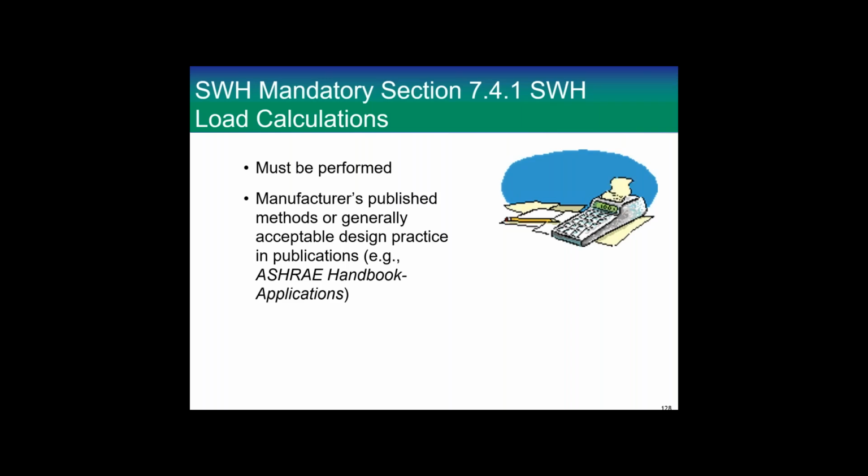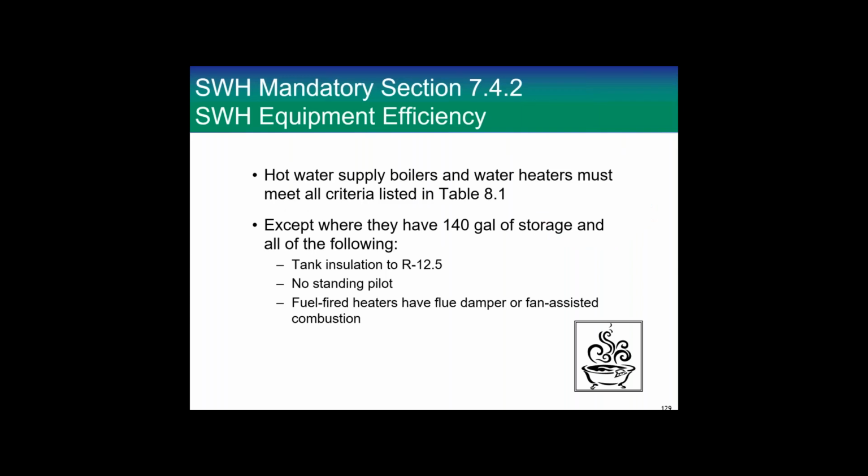We require you to run a load calculation for the hot water. Now, we don't require you to do anything with it. You don't have to meet the load. You can oversize, you can undersize. We can't really tell you what to do as far as that, but we want to assure that you've run it and you know the answer so that you're making wise decisions and you provide that to your owner, so the owner at least can follow what you're up to.